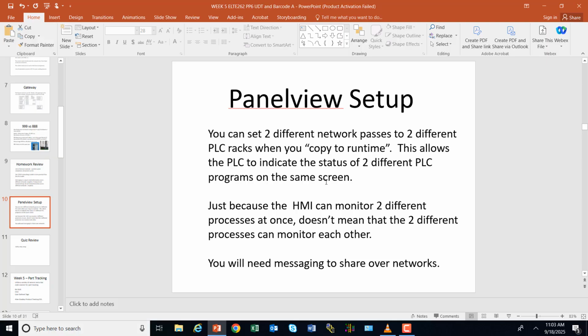So think about that. You can have a button on the screen running through the network pass to PLC 1, and then you have another button running through the network pass to PLC 2. So the panel view will indicate what's going on with two PLCs at once, even though they're not interconnected. And that's what I'm saying. Just because the HMI can monitor two different processes at once, two separate PLCs on two separate racks, that doesn't mean that the two different processes can actually monitor each other. So those PLCs don't see that.